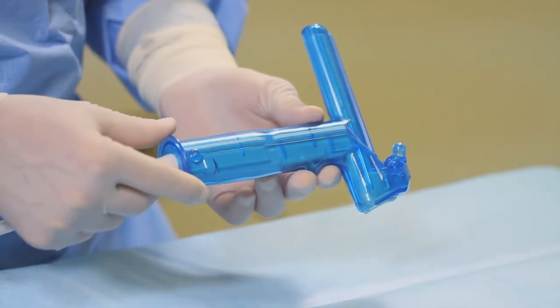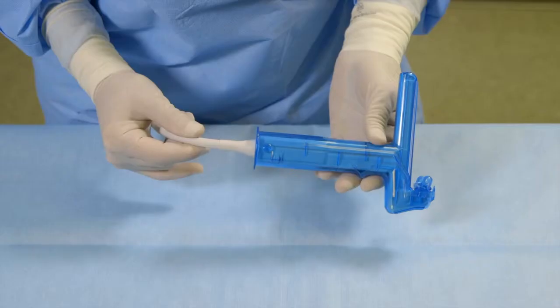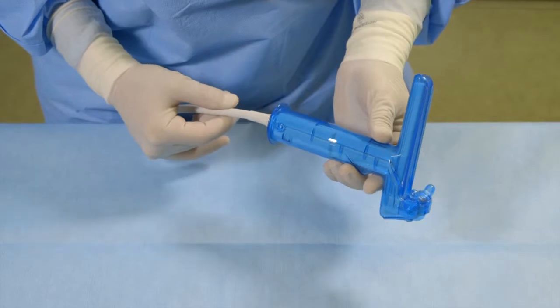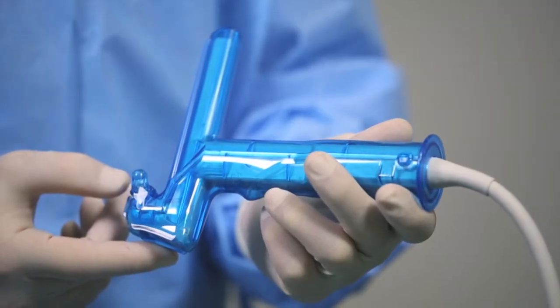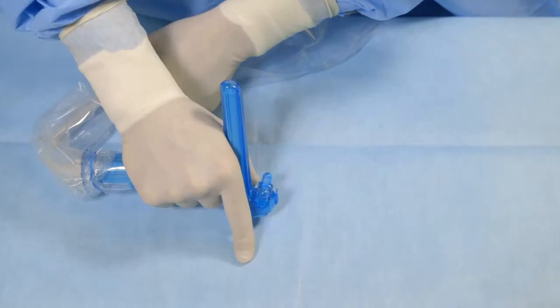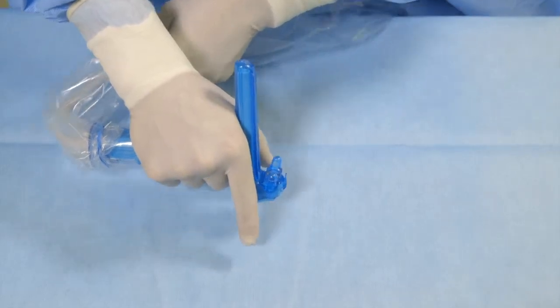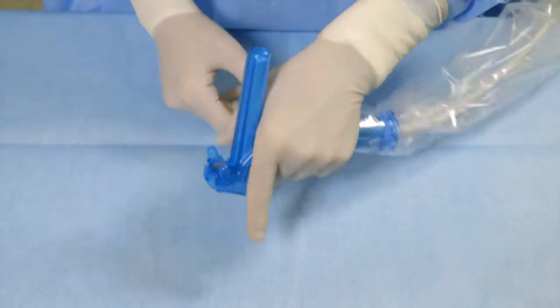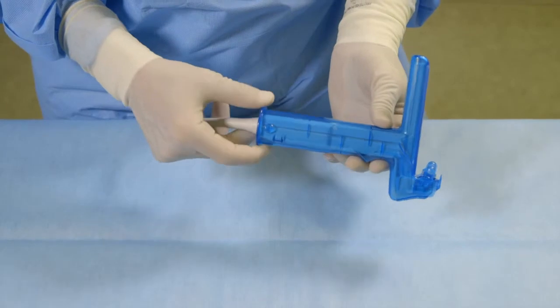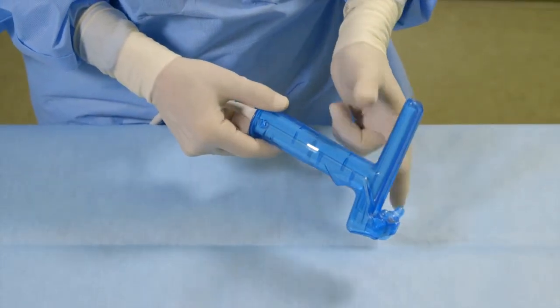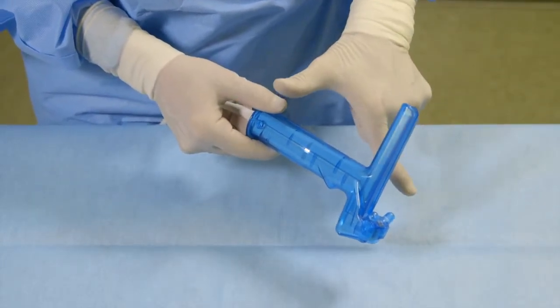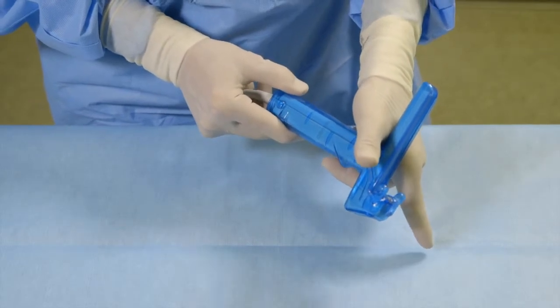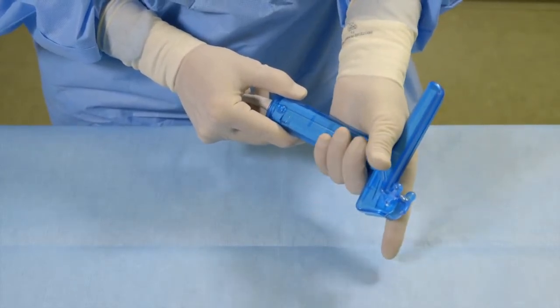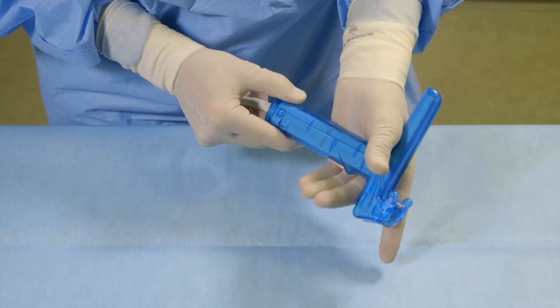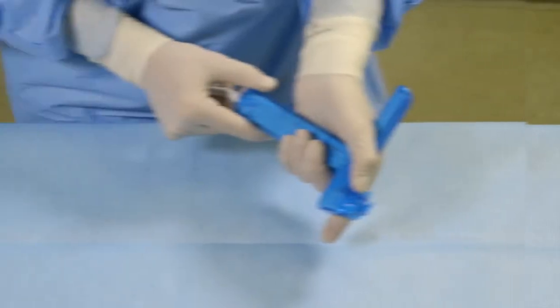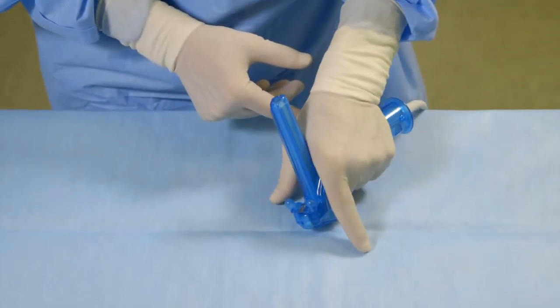The Sonosite AxoTrack-equipped transducer has a unique design that allows it to be held securely, facilitating accurate needle guidance. Once assembled with the transducer shield, the transducer can be held in either hand. For optimal stability during use, make an L with the thumb and forefinger and place it up against the vertical post. Grip the transducer with the middle finger in front of the finger guide. This leaves the thumb and forefinger free to act as stabilizers on the patient.